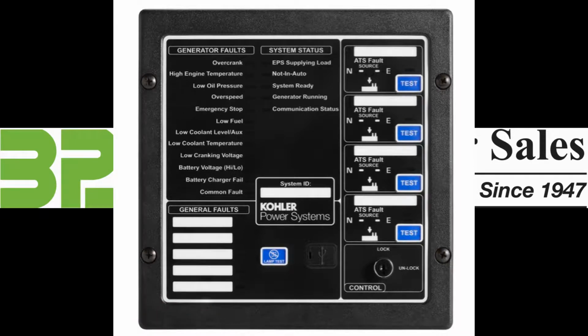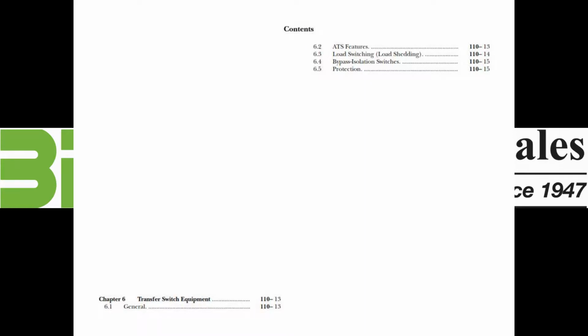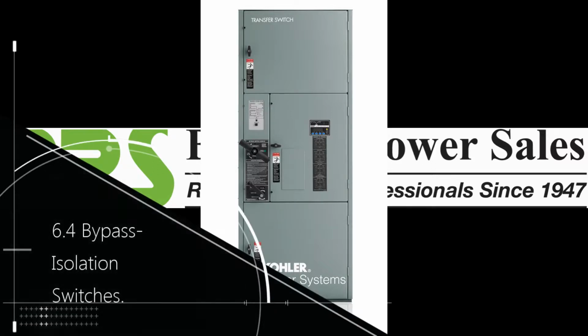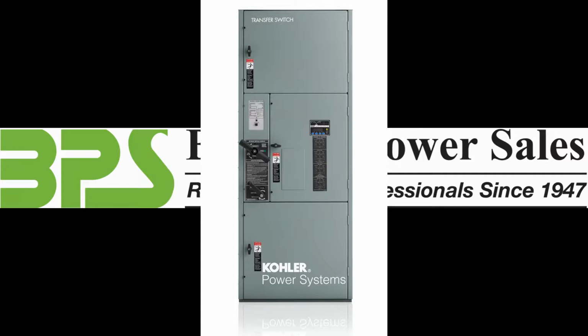The NFPA 110 covers transfer switch equipment in quite detail. Once again, this can be a topic all on its own, but briefly, in Chapter 6 is the bypass isolation switches, which are typically found in healthcare or data centers, those loads that are very critical and difficult to service and maintain. So let's focus in a little bit on transfer switches.